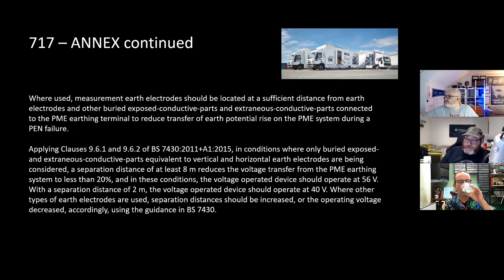It says in conditions where only buried, exposed, and extraneous conductive parts equivalent to a vertical or horizontal earth electrodes are being considered, a separation distance of at least 8 meters reduces the voltage transfer from the PME earthing system to less than 20%. And in these conditions, the voltage operated device should operate at 56 volts with a separation distance of 2 meters. Is this where we looked at the distance for electric vehicle charging point TT from PME? Yeah, it's all connected to it.